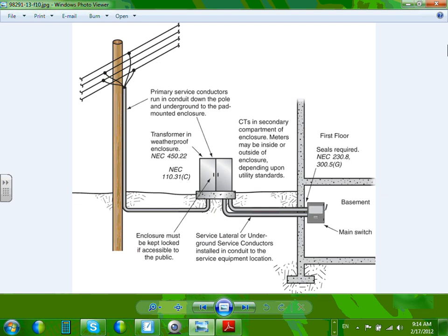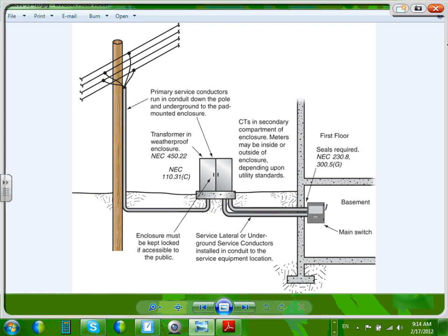Look what they do. You have the high voltage coming from here underground to the high voltage section of the transformer. This is primary service conductor. Primary service conductor coming in here, and from the transformer, you take it all the way to your main disconnect to the building.